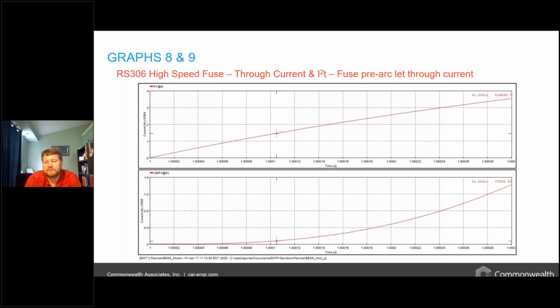And that's something that we have to investigate. We have an example of how we looked at it using some advanced engineering software. So here, what we're looking at is the I²t of the fuse, which is telling us how fast this fuse will have a melt and a total melt time before the fuse will completely clear the fault, and what the maximum fault current will be during this.